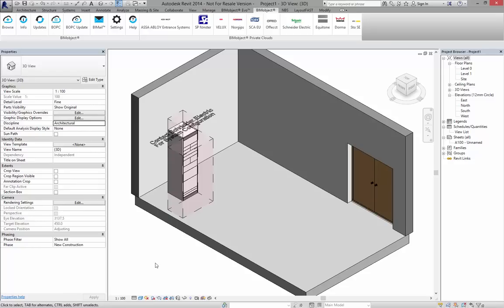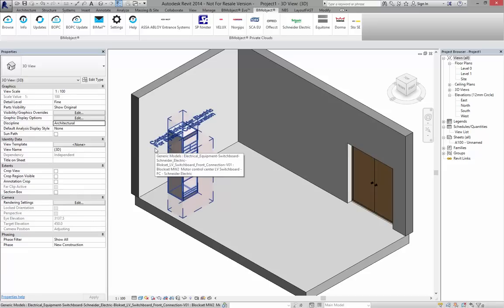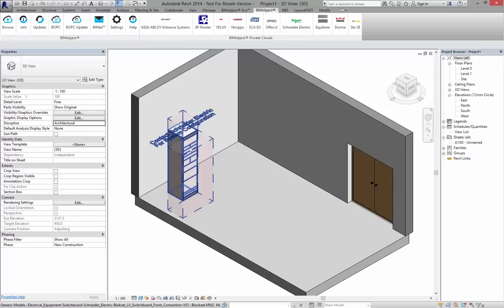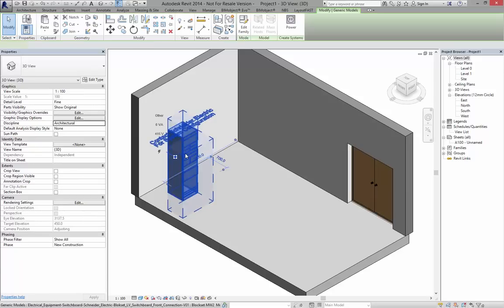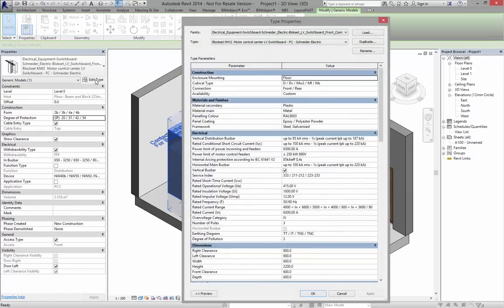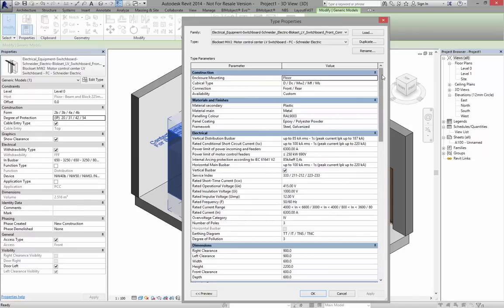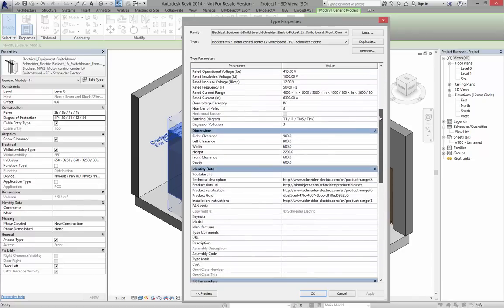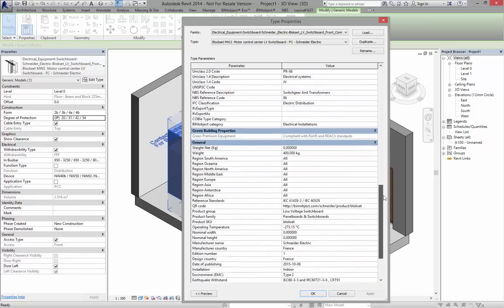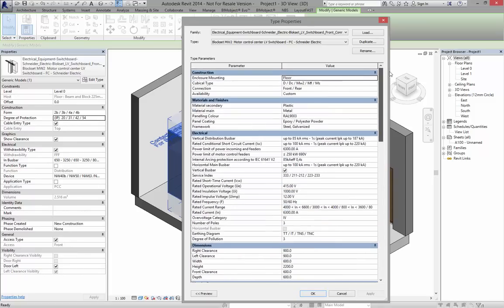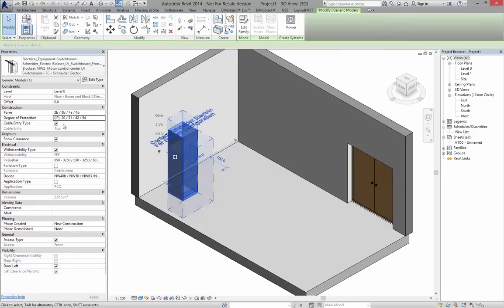We have here different parts of the geometry. We're showing in 3D the clearance zones, zones for access, and zones for air circulation which must be adhered to when placing these objects. Let's click on this and go into the edit type information. You can see we have a huge amount of electrical data regarding its outputs and requirements, and we also have all the BIM object information in there as well.